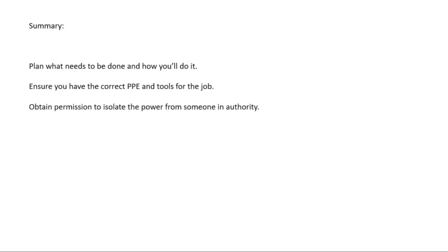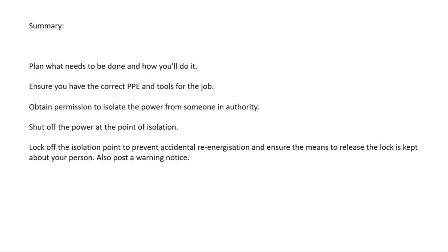Obtain permission to isolate the power from someone in authority, in writing if necessary. Make sure the client is aware of how long power is likely to be removed for and what may be affected. Shut off the power at a suitable point of isolation. Lock off the isolation point to prevent accidental re-energisation and ensure the means to release the lock is kept about your person. Also post a warning notice.